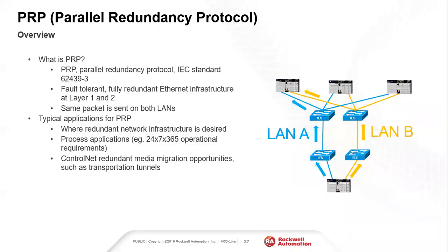So this is a newer feature, something that's probably within the last year is starting to take hold. Parallel redundancy, or PRP for short. This is another way of doing the same type of networking, but the difference is instead of a ring topology, I'm looking at 2 ports sending the same data out both connections. Similar idea to the redundant star. It might be easier to implement. There might be more pieces I have to deal with, but now if I lose one leg, I'm still communicating off the other.